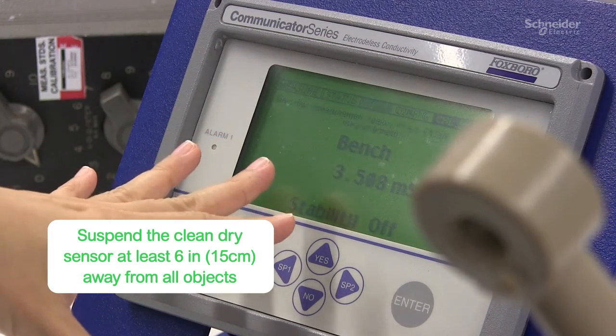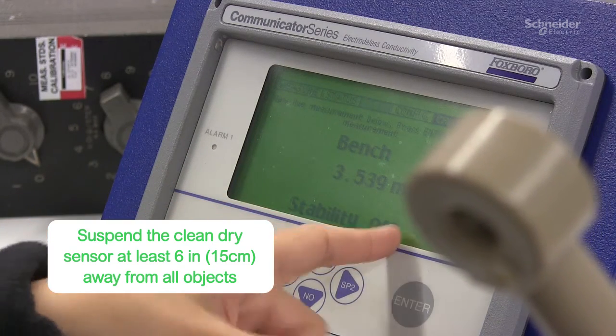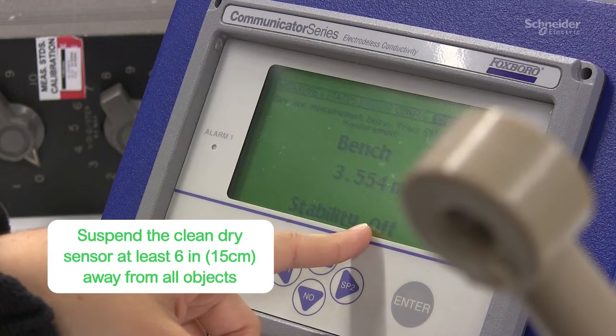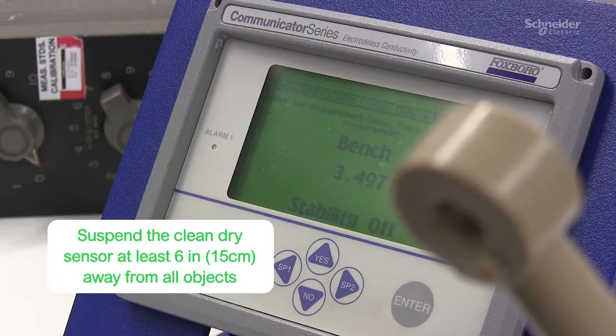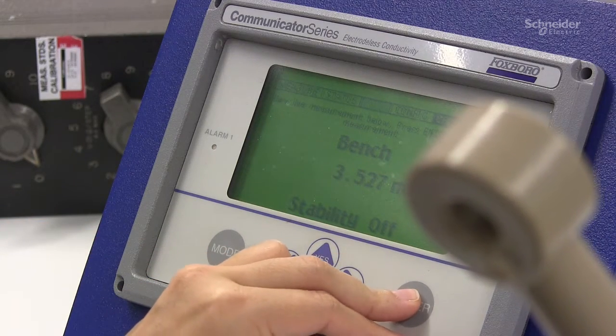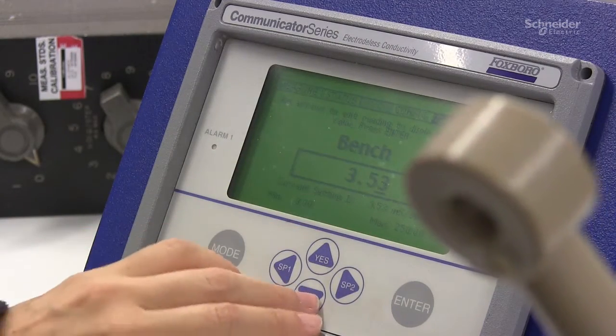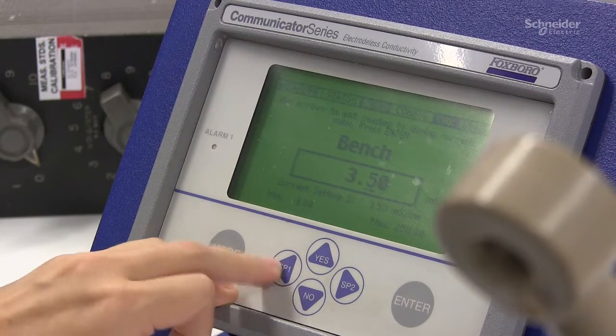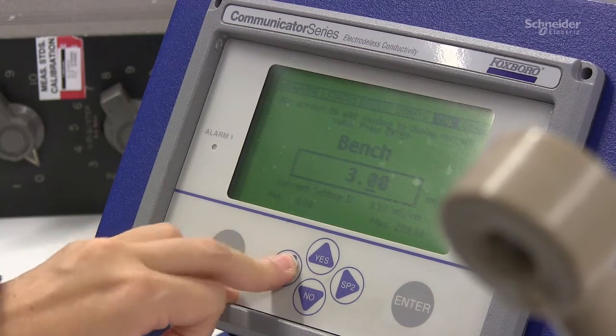Wait for a few moments. It will read stability off if you have not configured for it to be auto, which is our case. So after you give it a few moments for it to stabilize as much as possible, press enter and manually change that number to all zero. I'm going to press the left arrow key to go to the next digit until they all read zero.